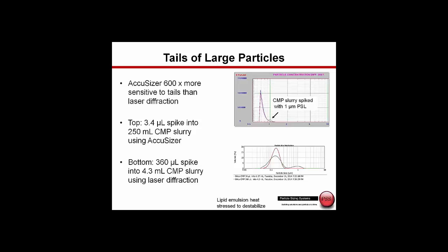One of the real strengths of single particle optical sizing is the ability to be able to measure a few large particles, the tails of distributions. I show one example here. This is actually a sample used in the microelectronics industry called a chemical mechanical polishing slurry. In the upper right, what we see is an AccuSizer result. We took a 1.36 micron polystyrene latex standard, took 3.4 microliters of the standard, spiked it into 250 ml of the CMP slurry, and found this additional peak. We then took the same CMP slurry, measured it on a laser diffraction analyzer, and before we found the second peak, we had to spike 360 microliters into only 4.3 ml of the CMP slurry. This proves that the AccuSizer is over 600 times more sensitive to the presence of a few large particles than the laser diffraction technique.